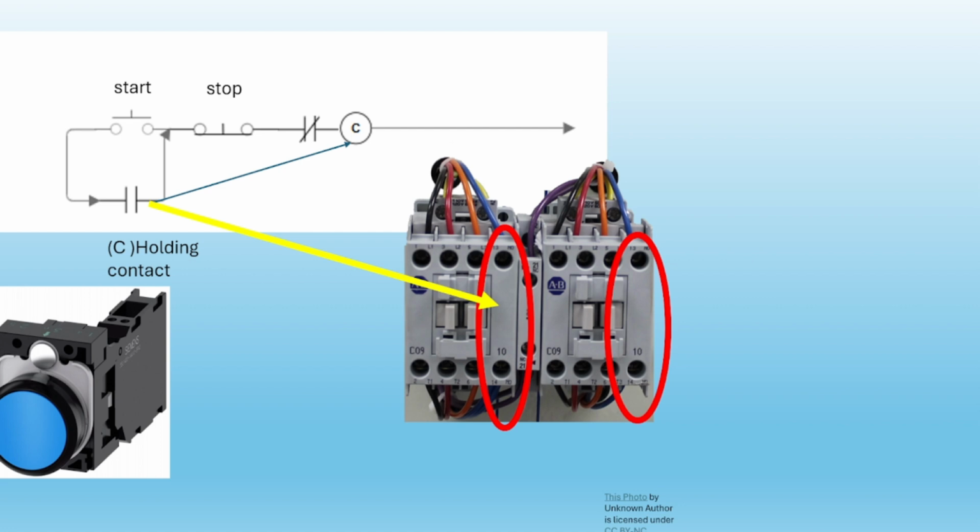C for contactor. This contactor is going to hold itself in. I hit start. Power will be pushed through, pulling this contactor in. This right here will hold it and keep it holding until you hit that stop button. This is your basic 3-wire start and stop system. That is another manual way of being done. It is easy to use. This is so quick to be put together, showing how to do different systems.